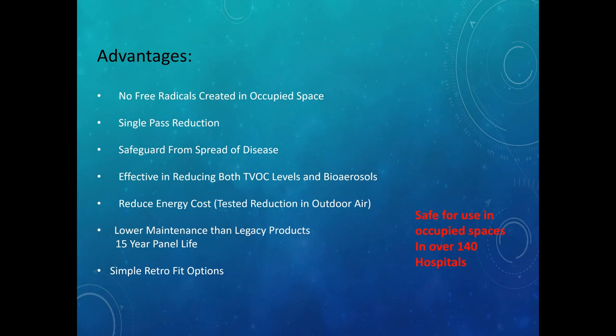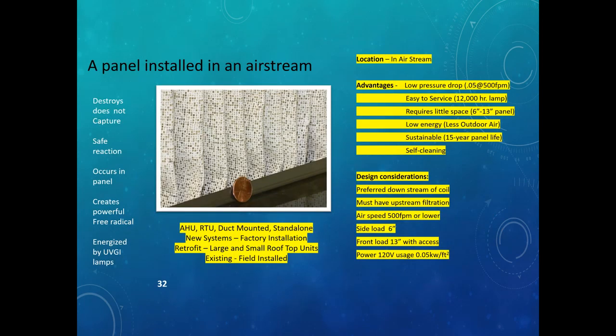It's not limited. And as we get ready to close here, I'll just quickly review. It destroys, it doesn't capture. The reaction is safe because it occurs in the panel. We create free radicals, which is the basis of most new technologies. You're creating an oxidizing agent that does an oxidation reduction reaction, so you probably need to be aware of where that's happening. The energy for ours is a UV lamp, and that is germicidal. So when you put it in an air handler, if you can position it in the saturated zone, where it shines on the surface of the coil, it will keep your coils clean, lower your TVOC count, and reduce your bioaerosols.